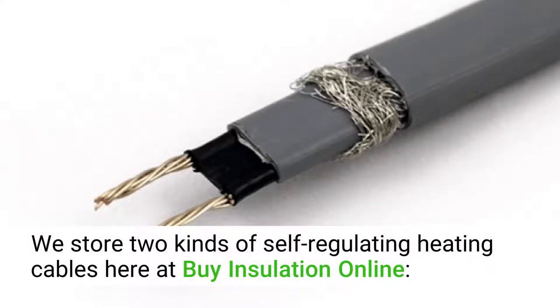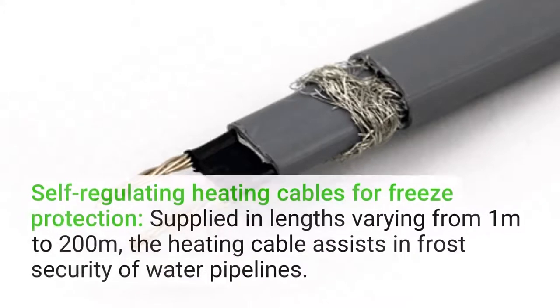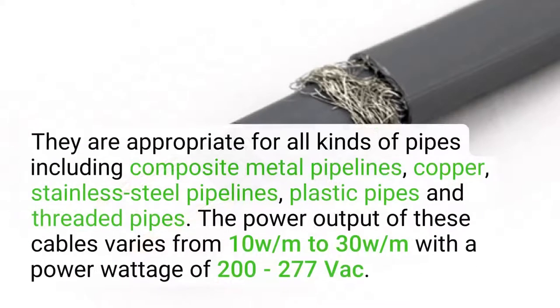Buy Insulation Online stores two kinds of self-regulating heating cables. Self-regulating heating cables for freeze protection: supplied in lengths varying from 1 meter to 200 meters, the heating cable assists in frost protection of water pipelines. They are appropriate for all kinds of pipes including composite metal pipelines, copper, stainless steel, plastic pipes, and threaded pipes. The power output varies from 10 watts per meter to 30 watts per meter, with a power voltage of 200 to 277 VAC.